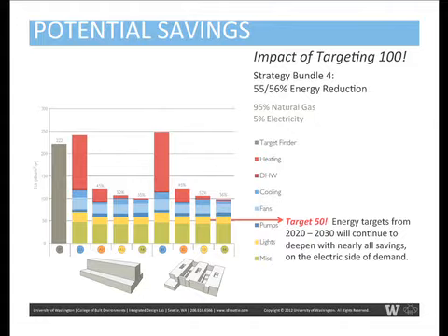So we're close, and we're hitting the targeting 100 goal in New York. Another thing to point out here is the relative similarity between Scheme A and Scheme B in the energy results. There's a modest difference, but essentially we chalk that up to them being really internally load-dominated buildings, so there isn't a big energy difference. The good news is having a more articulated envelope is not an energy penalty, which you might think, because there's more envelope, potentially more heat loss or heat gain, but it actually works well. And as we move beyond targeting 100, say targeting 50 or targeting 0, this more articulated form gives us more resilience to be able to do that. There's more options on the daylighting side. There's potential for natural ventilation.